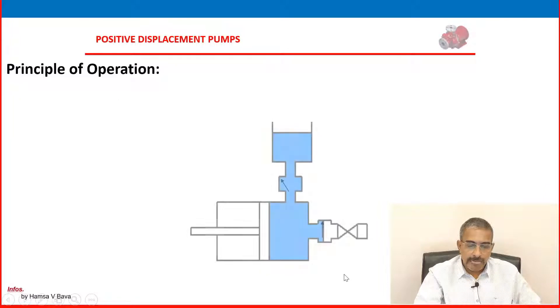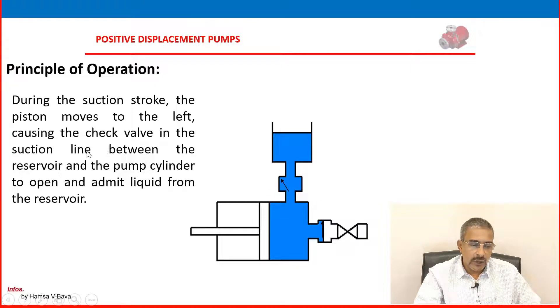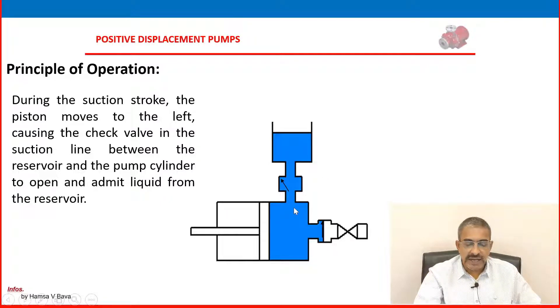During the suction stroke, the suction check valve is in the open position and the discharge check valve is in the closed position. The piston moves to the left, causing the check valve in the suction line between the reservoir and the pump cylinder to open and admit liquid from the reservoir. This is how the piston and cylinder reciprocating pump works.